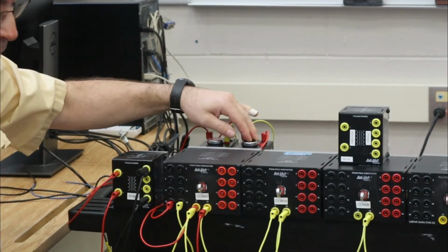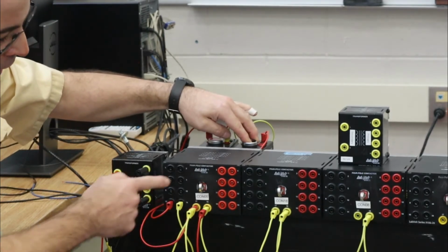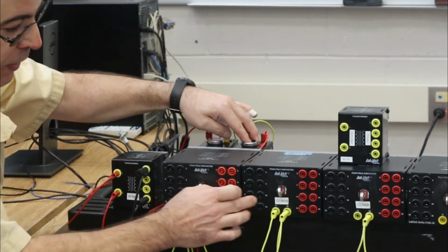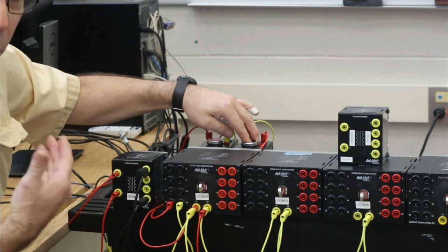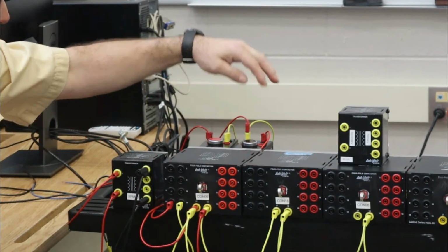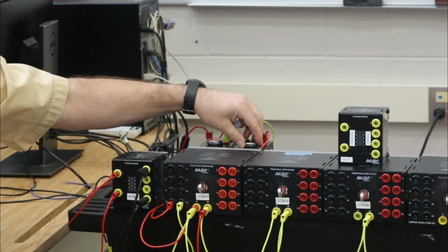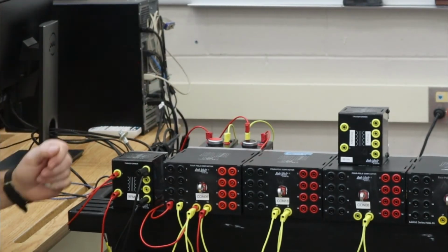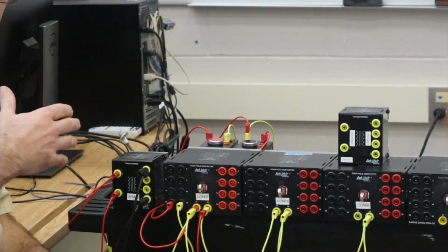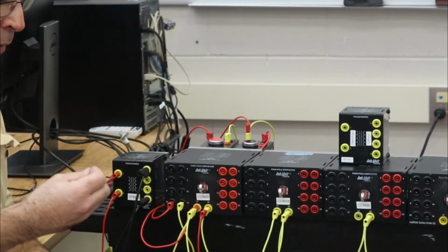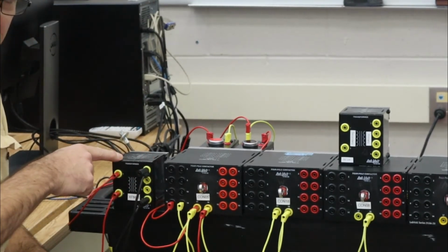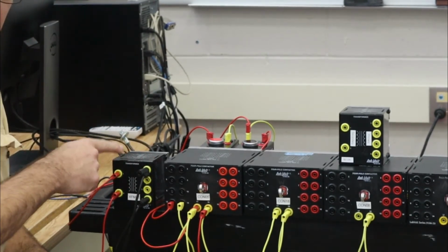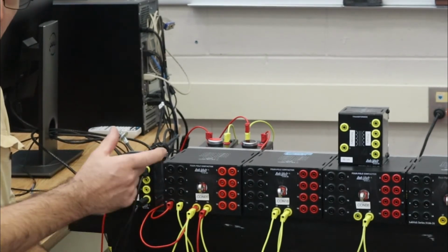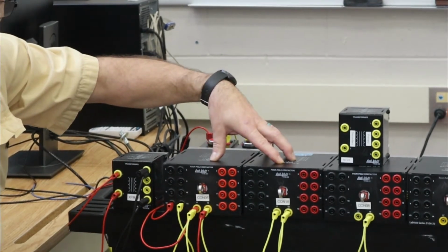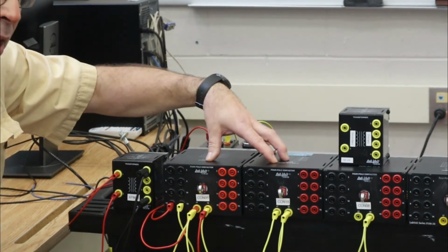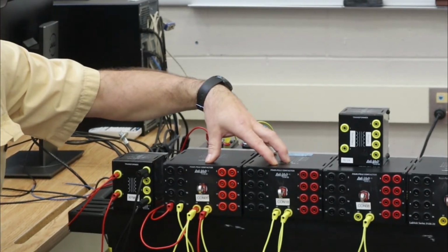Let's do that again. Now what you can see is that there is a little bit of travel in between both of the armatures. There's a real audible noise, and the fact is when I release pressure on the start push button, everything is reverting back to its shelf state, which really goes to prove the theory that a 25 VA transformer does not have enough to deliver the inrush current required to get these two relays to change state, much less have enough power to maintain them in that state.